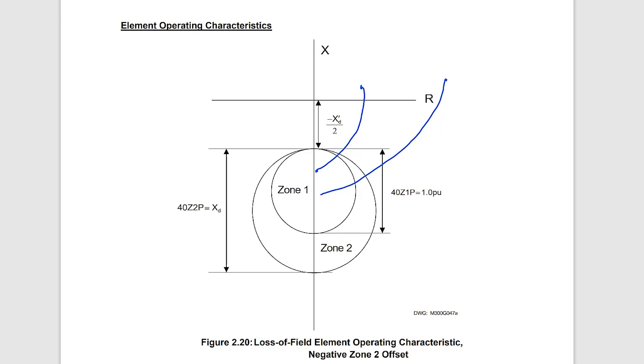Typical settings are to set the negative offset of the mho elements to half the direct axis transient reactance — that's ½ X'D. The zone one element diameter is set to one per unit on the machine's base, and zone two is set equal to the direct axis synchronous reactance XD. This ensures that all cases of impedance trajectory, whether the machine is unloaded or heavily loaded prior to the loss of field condition, are covered.